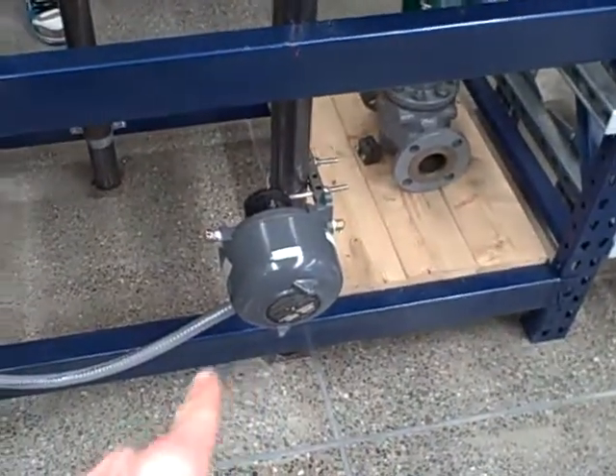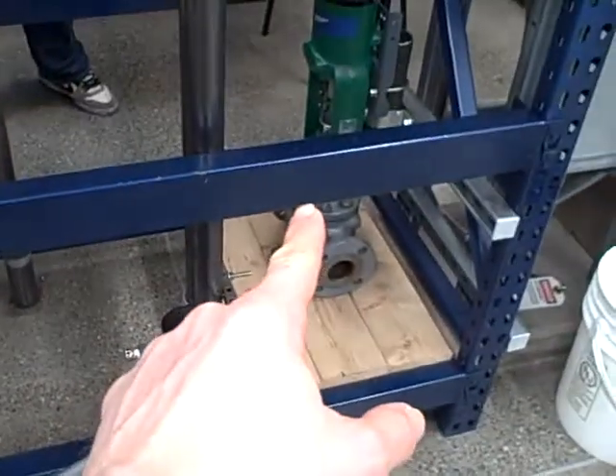They're now doing the wiring on the I-to-P converter to send air pressure to that valve. They're documenting the wiring here on the terminal strip. They're going to be doing a loop diagram and making sure all the wires are properly labeled and documented as to where they go.